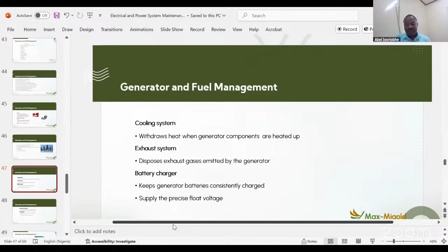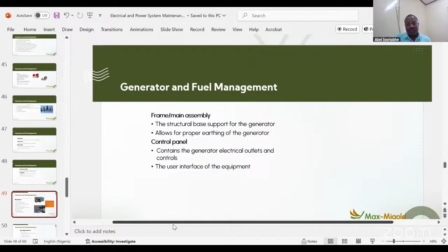Control panel: also ensure the connections are firm, they are tight, no loose connections. If there's no proper connection, there will be an open circuit and your generator will not work. That's why somebody will bring a computer and start troubleshooting, whereas it's just a simple wire that lost connection, and they will come and charge you millions. Because of your ignorance or lack of attention, you will end up spending millions you are not supposed to spend. So we are employed to bring value to our facility.